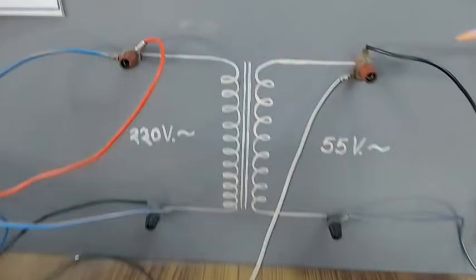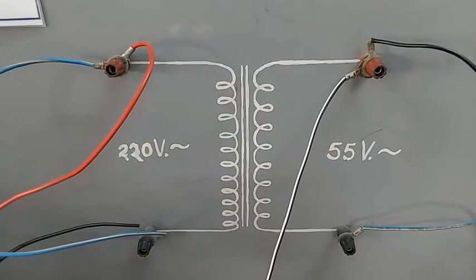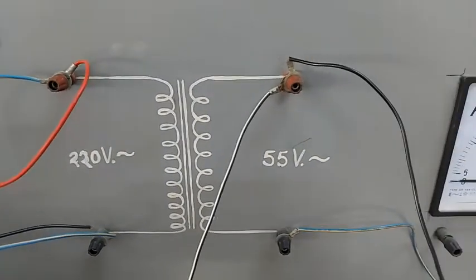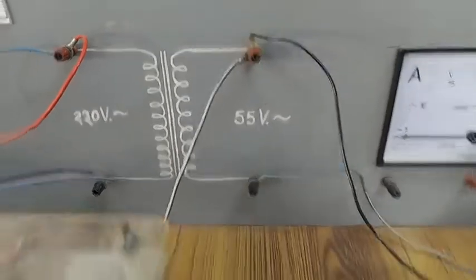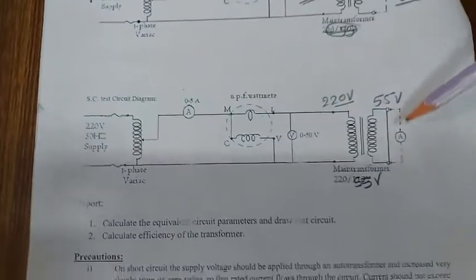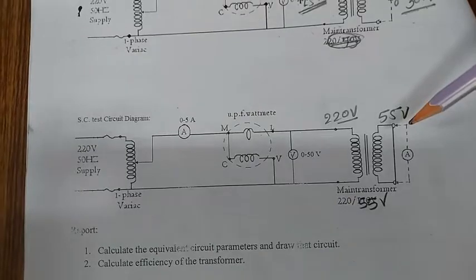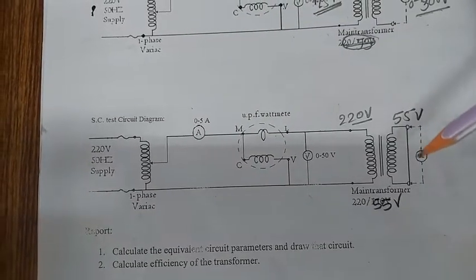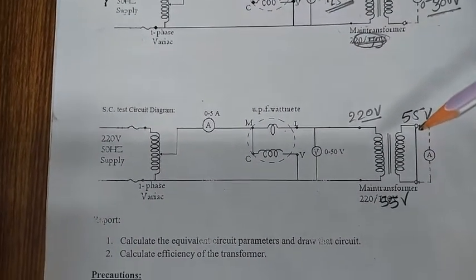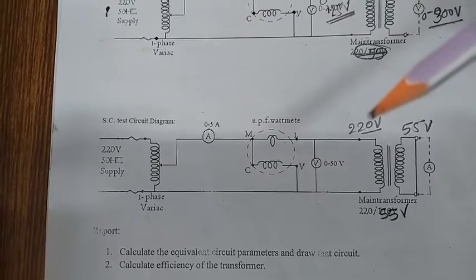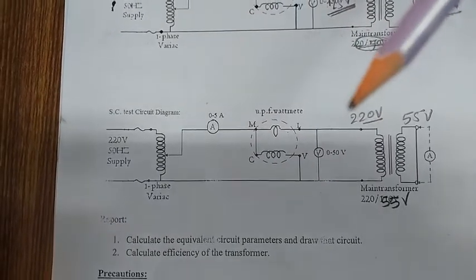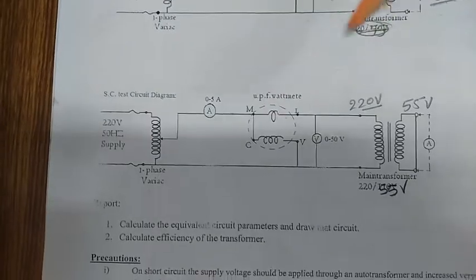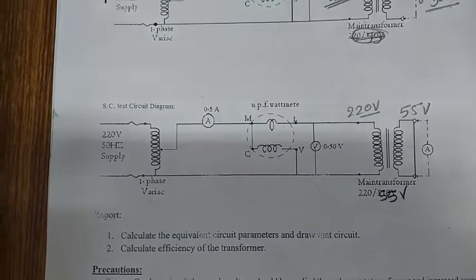So here we also see from the panel that 220 volt is the high voltage side and 55 volt is the low voltage side. Now, as a thumb rule, we will short the low voltage side. That means we will apply the power to the high voltage side, that is the 220 volt side. So that power will be consumed as the full load copper loss of the transformer in this short circuit test.